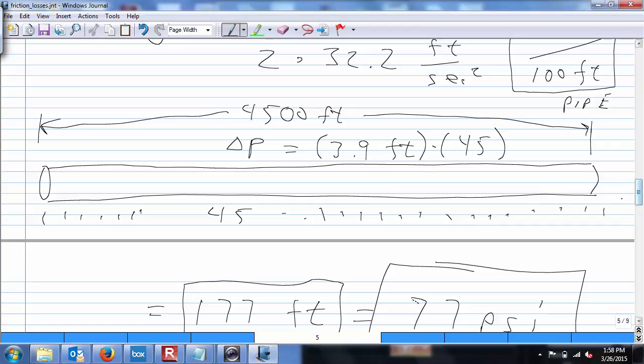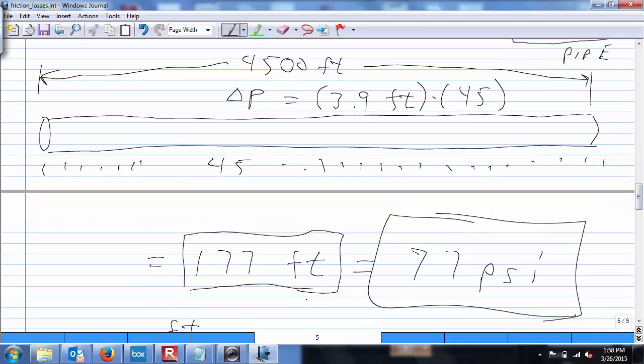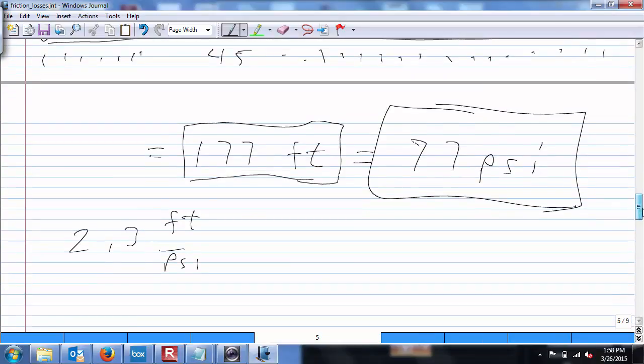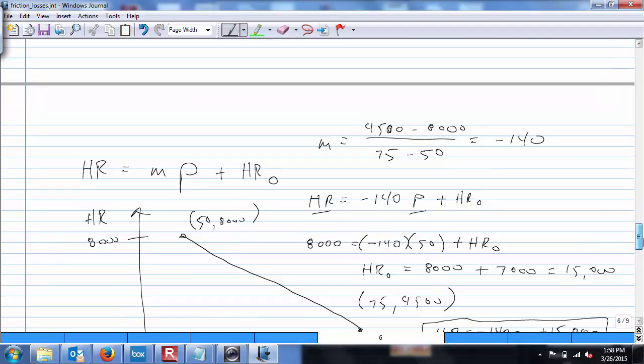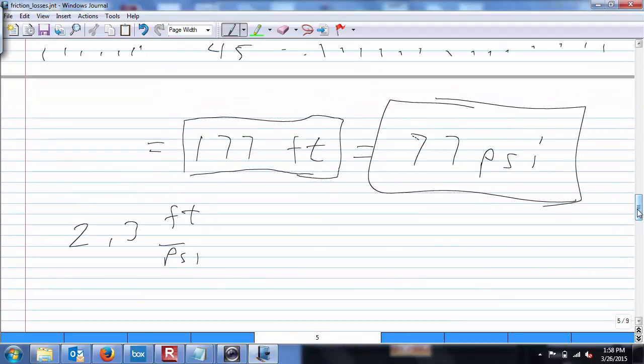And then we take our 177 feet of head loss, that converts to 77 PSI. We didn't actually need the PSI in the calculation, but there you go. Yep. Did you square gravity? Okay. That's enough to be dangerous on that, I think. So, first problem. Okay, cool.